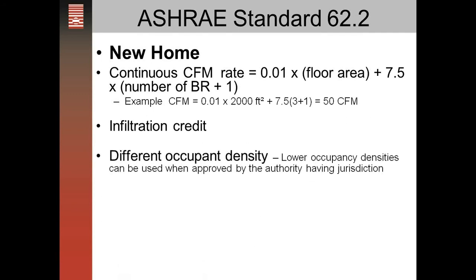If you have a different occupant density — for example, if you have one person in a house — you can lower the occupant densities if you have approval from the authority having jurisdiction. So in the example we used above, that 50 CFM rate could be less if there's only one person in the house, as long as the authority having jurisdiction is okay with that.